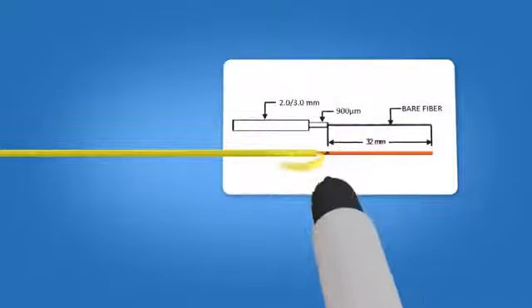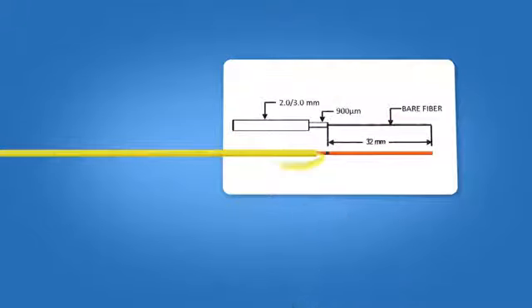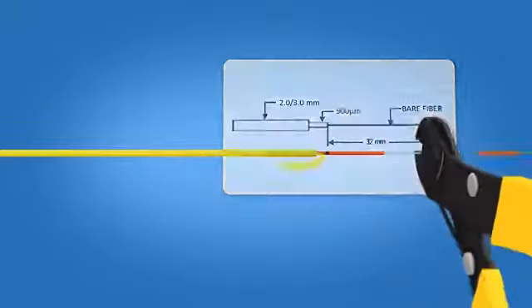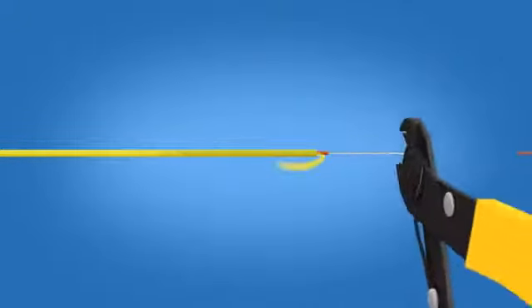Using the template on the front of the connector packaging, mark the fiber at 32 mm from the end of the 900 micron fiber. Strip 32 mm of 900 micron and 250 micron coating off, exposing the bare fiber. Clean the fiber with a lint-free wipe and fiber preparation fluid.